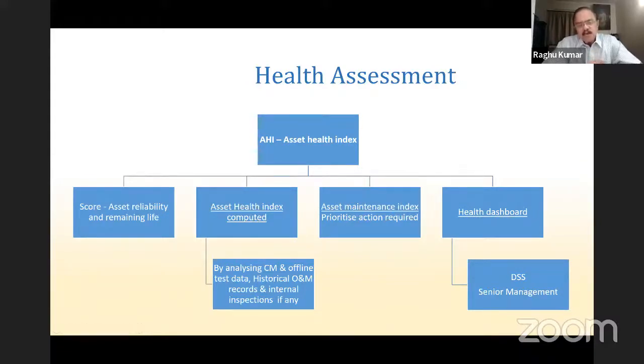This index gives you, for a particular zone, the whole area being divided into multiple zones, the maintenance requirement of the transformers in that zone. It is prioritized: which transformer is worse, which is in good condition, which needs to be attended as early as possible. These scores are available in the asset maintenance index. And this asset health index is taken from condition monitoring data, offline test data, historical data, and internal inspections, if any, carried out. Finally, this health dashboard is the one which is useful for the top management and senior level management. Here, in one single picture, you get fleet information of the total transformer health. And whenever the maintenance people want a budget for a major repair, this health dashboard is a supporting document. It's a decision support system.